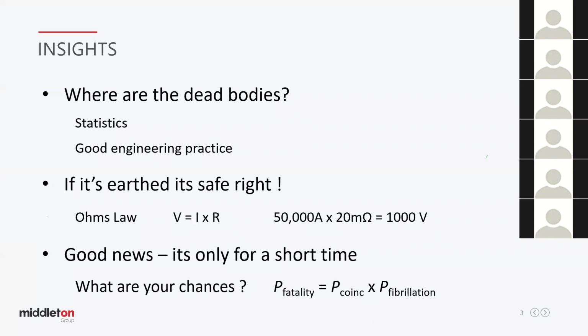A lot of us go, well, if it's earthed it's safe, right? Hold on a sec. Well, perhaps not. Someone just helped me out there. The old Georg Ohm back in 1827 came up with a very simple formula, and it's very good to use this simple formula in earthing. It reveals a lot of things. So let's say, for instance, we all would think that from a resistance point of view, something less than 1 ohm is pretty low resistance. In fact, 20 milliohms, as I've got in the formula there, is quite a low resistance.